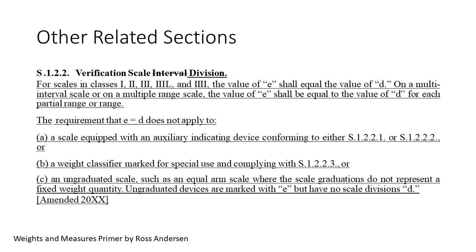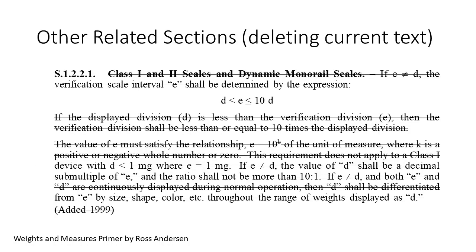One final note, Class 3L is part of the norm where E equals D. However, I will explain in Part 3 that the tolerance structure has been changed to allow many more E's of tolerance. This turns out to be equivalent to having D less than E for an equivalent Class 3 instrument.